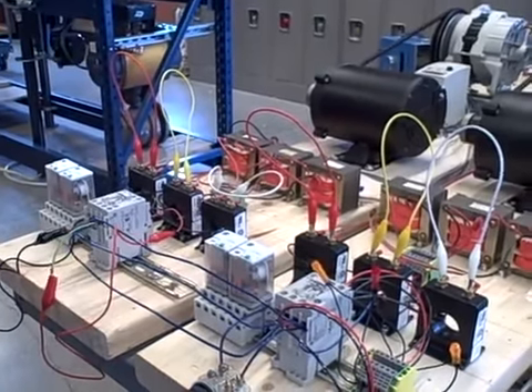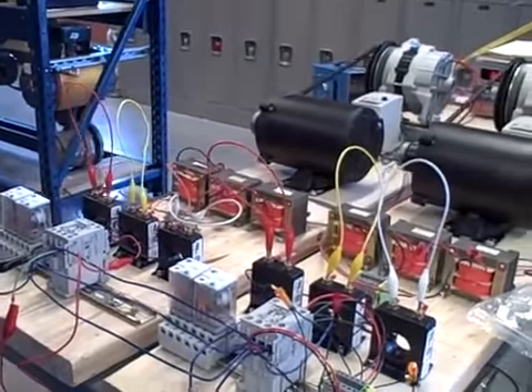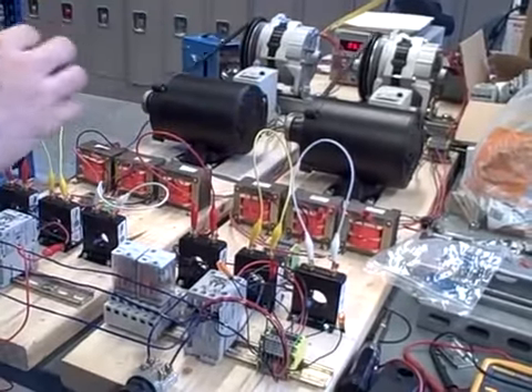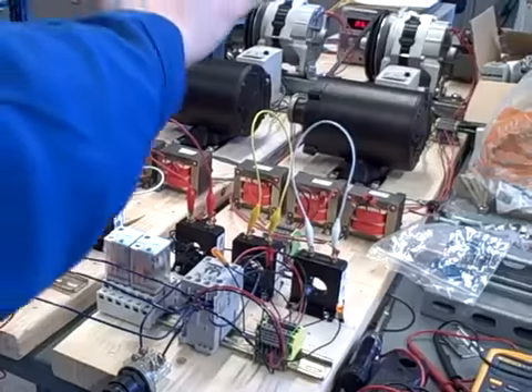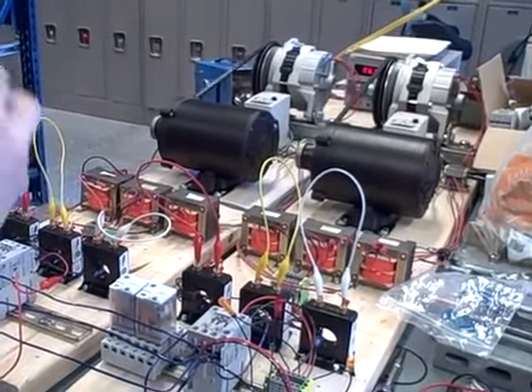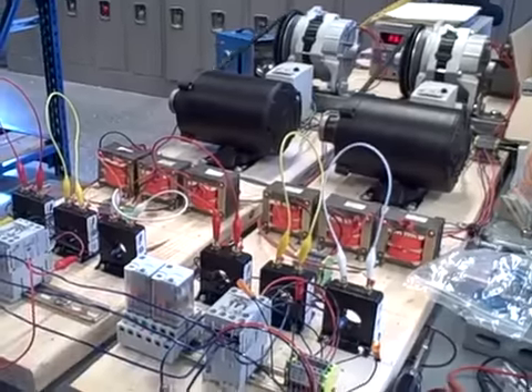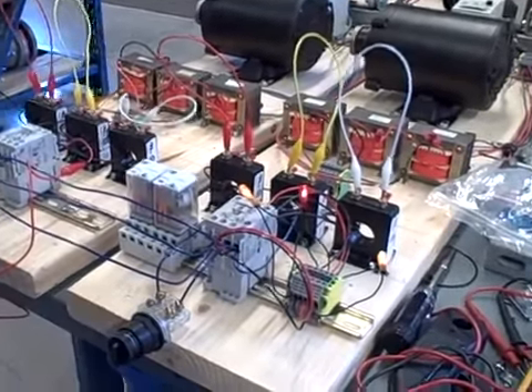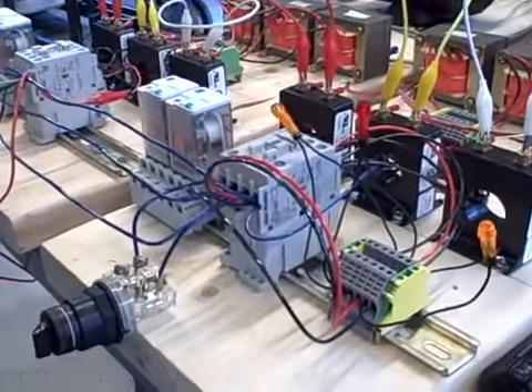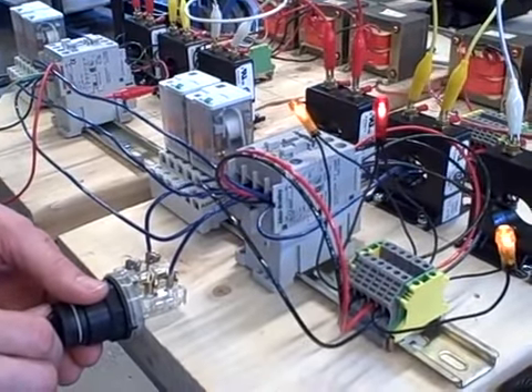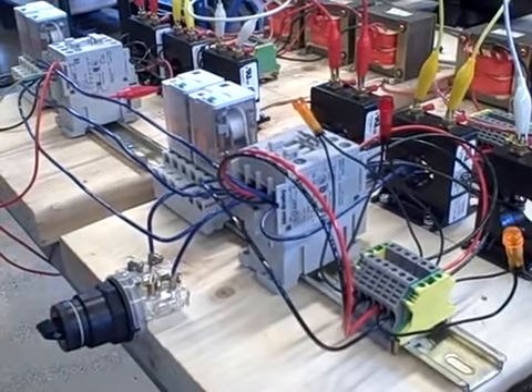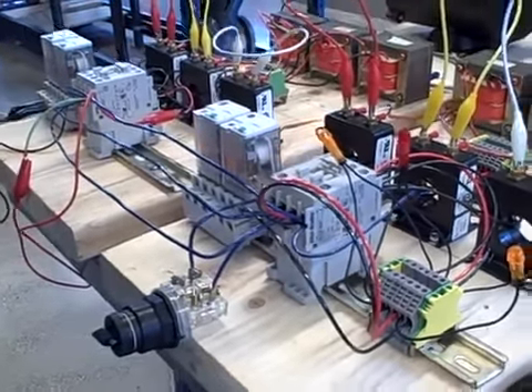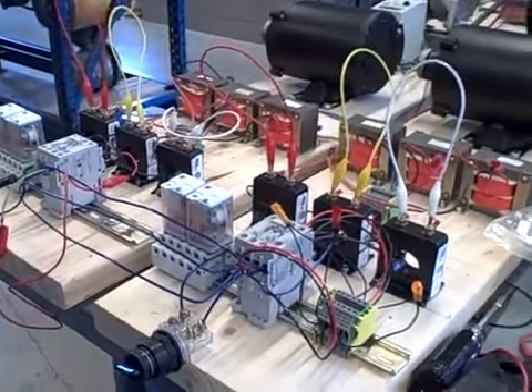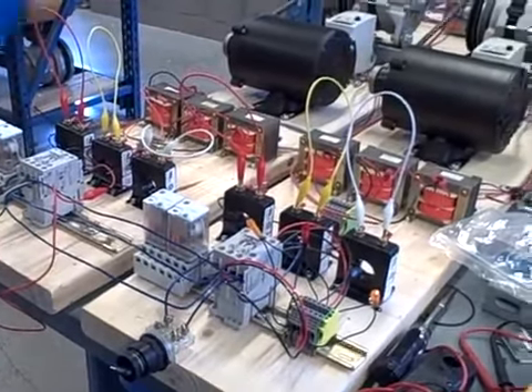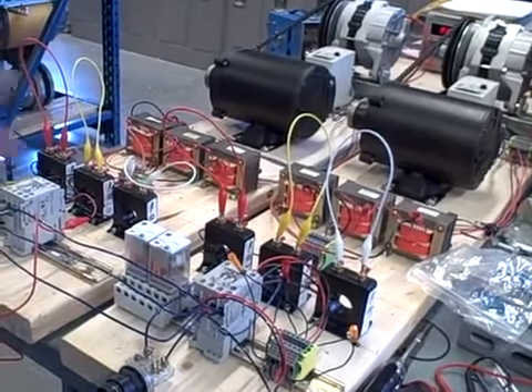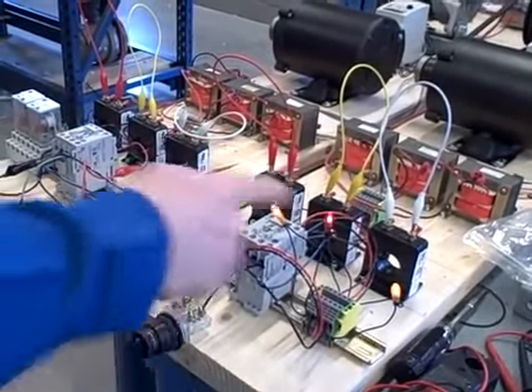So right now, when we have them in sync, and we have these two induction motors powering them, the ability of the induction motors here to slip is what allows these two generators to actually stay in phase with each other, even though the motors would actually be having them spin slightly different speeds if left to their own devices. I can unsynchronize the generators here, and you can see I go back into a condition where they're rolling in and out of phase with each other. I can go synchronize again, right there, and now they're synced with each other, and they're going to stay locked in sync unless I were to shut one down completely, because one generator in this case does not have enough current capacity to keep the other one going as a motor. So that's a demonstration of synchronizing two generators and using sync lights to do so.